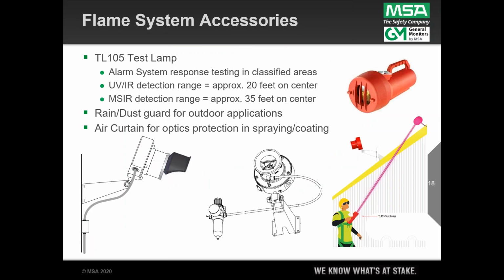As far as accessories, we've got a test lamp called the Model TL105, and this allows on-demand alarm system response testing in your hazardous area. Maximum range with our UVIR detector is going to be about 20 feet on center, and that's with a full battery charge, with the windows clean, with the high sensitivity setting. With MSIR, we'd see a maximum of 35 feet on center, again with clean windows, full charge, and everything set up properly. We also have a rain and dust guard, and I'll tell you, for every outdoor application, I recommend that accessory. That helps keep dirt, dust, and contamination off the window.